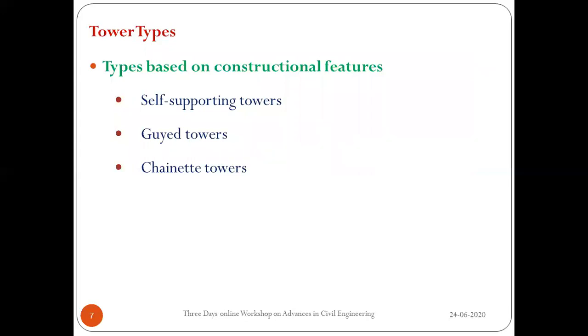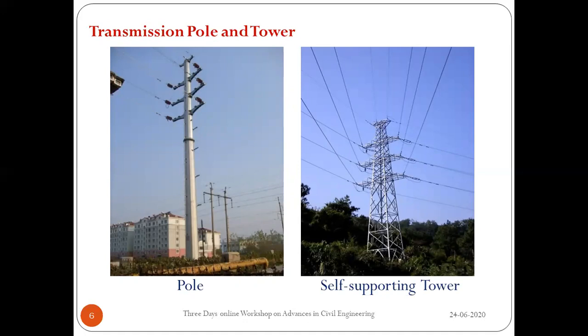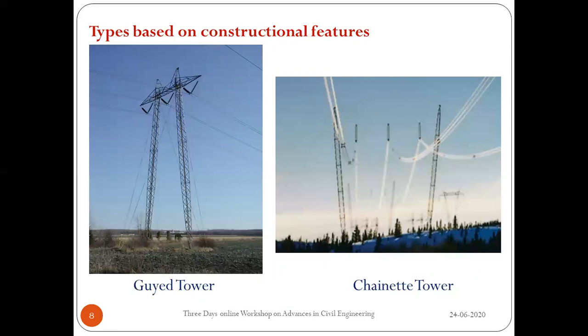Tower types based on constructional features: self-supporting towers, guyed towers, and chainette towers. Self-supporting towers don't need additional support — they stand with the help of four legs and the lattices. Guyed towers have a beam at the top with two-column arrangements supported by guys on all sides, attached to the ground to prevent overturning. Chain towers use guys from which insulators are hung for power transmission, without a steel beam at the top unlike guyed towers.